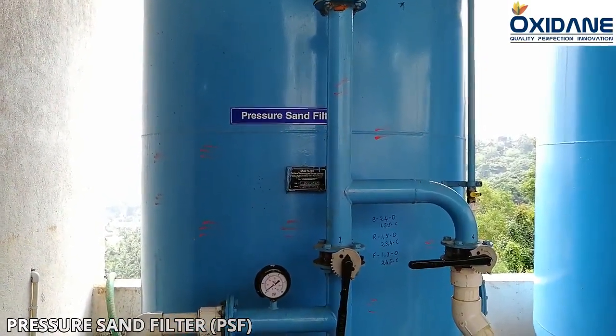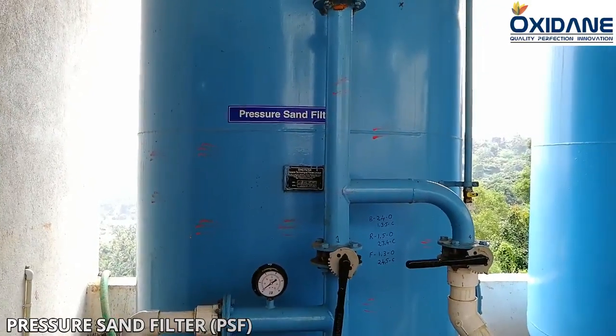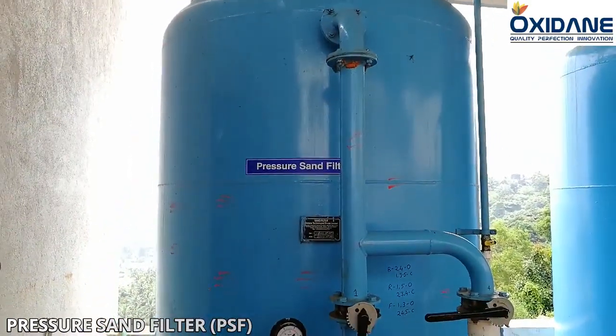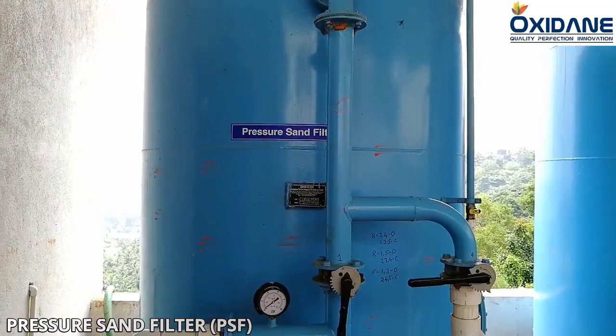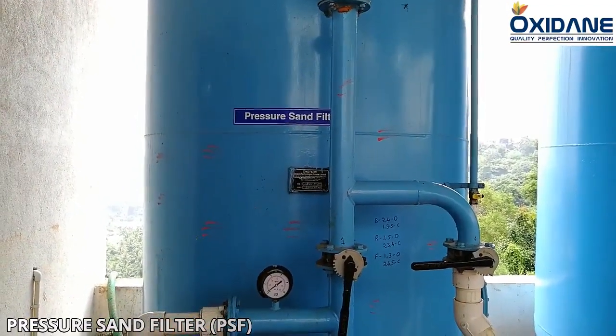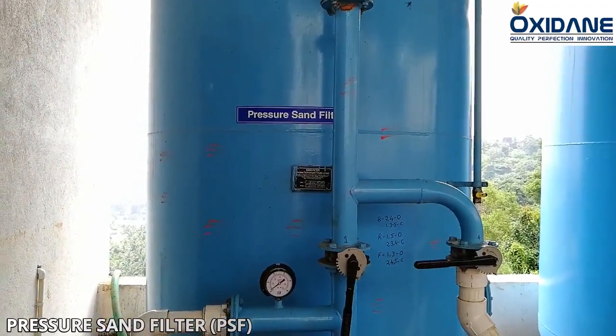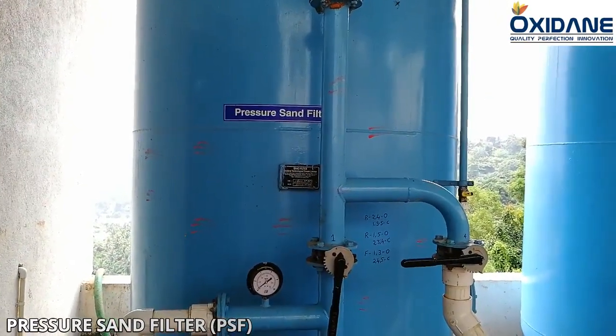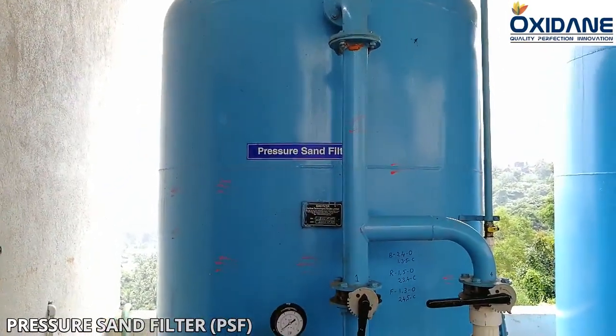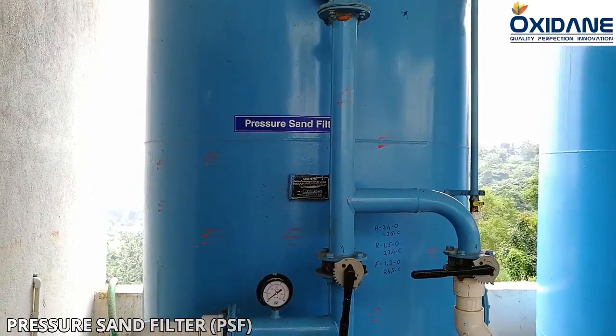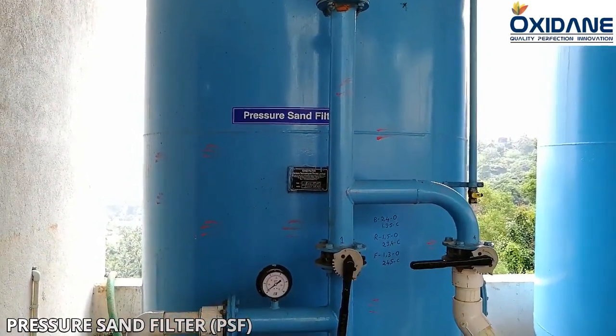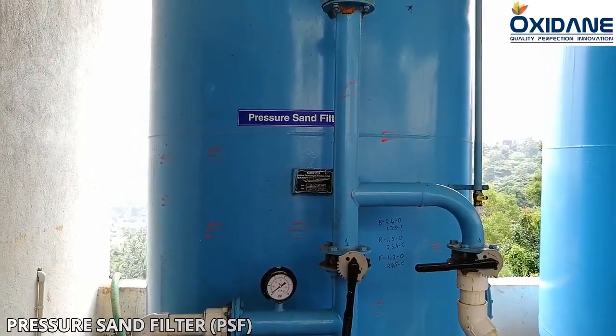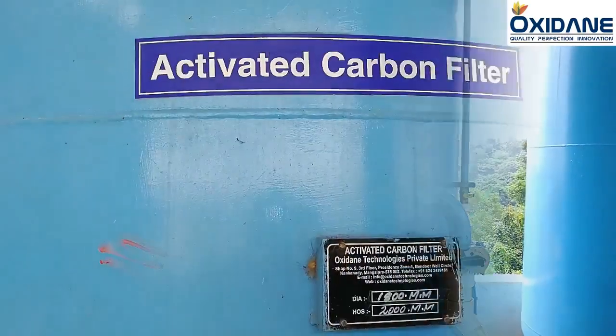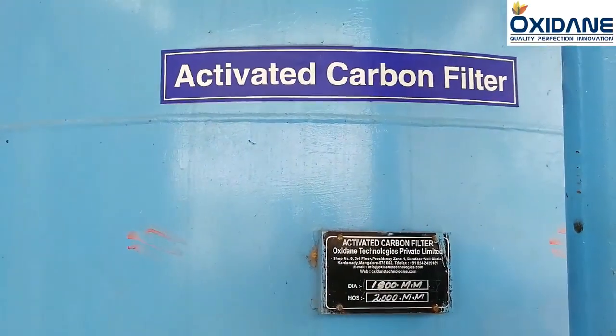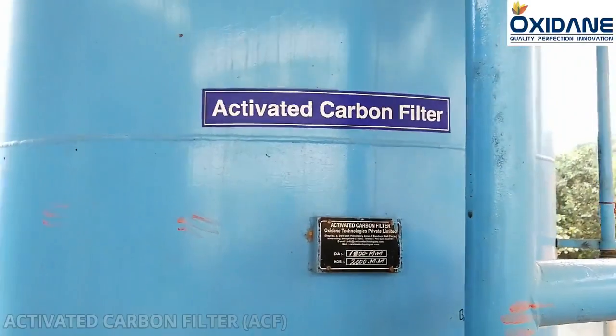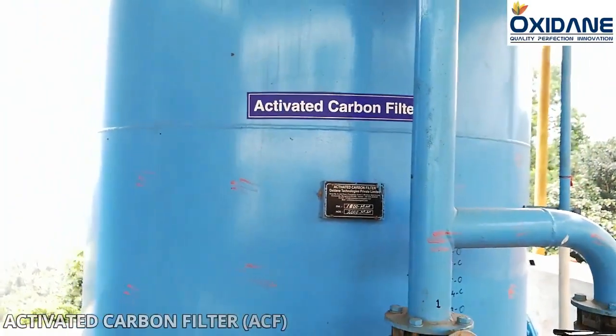The pressure sand filter consists of a multiple layer of sand with a variety in size and specific gravity. These filters are designed to remove turbidity and suspended particles present in the feed water with minimum pressure drop. These filters are custom designed to suit the process requirement. These filters are offered in mild steel, FRP or SS construction with face piping and associated valves. After its process, the filtered water will be sent to activated carbon filter, or ACF for short.